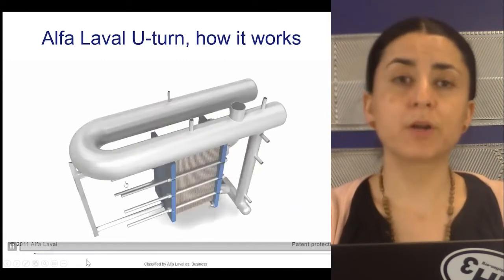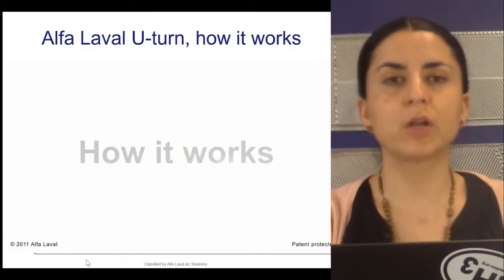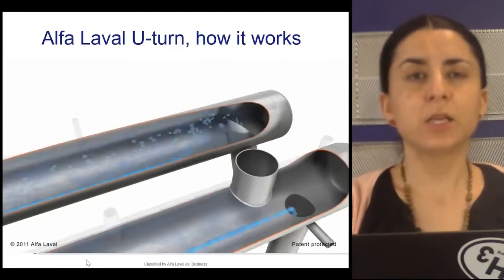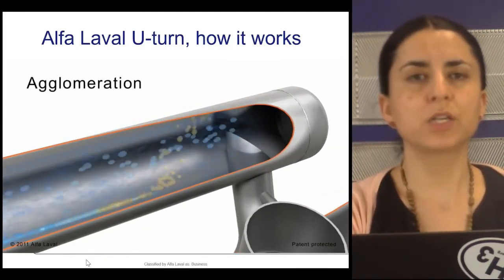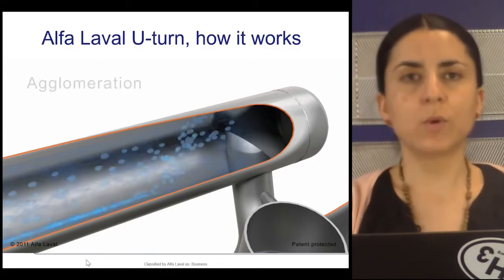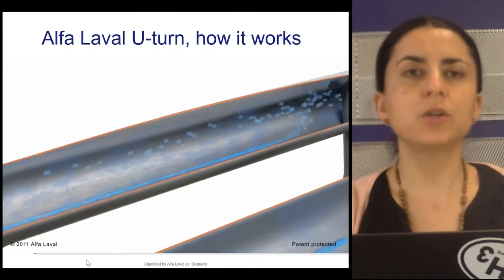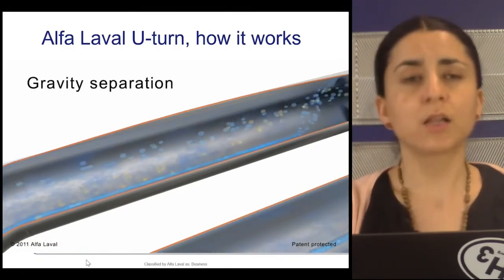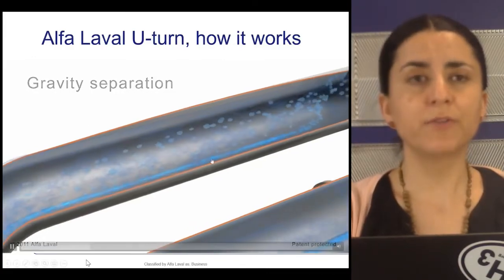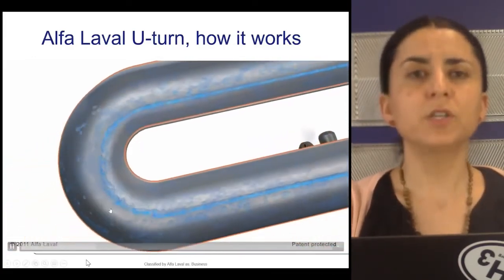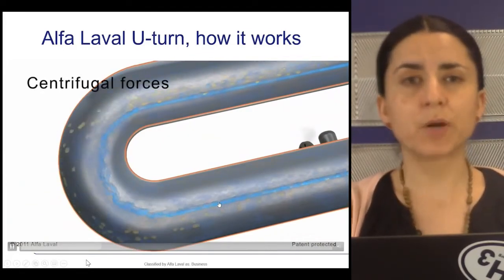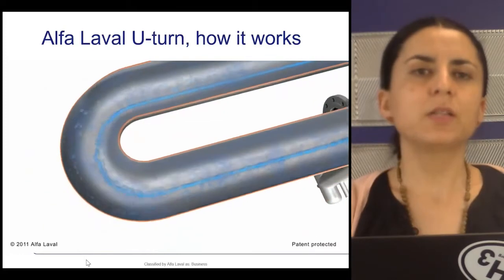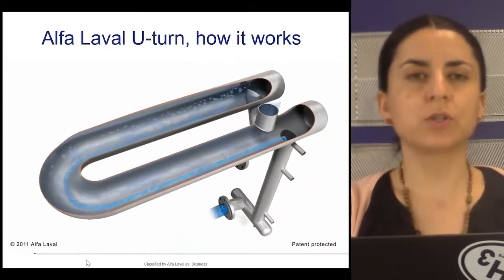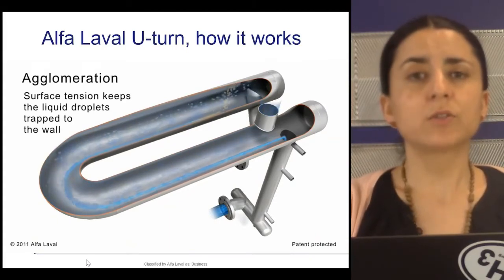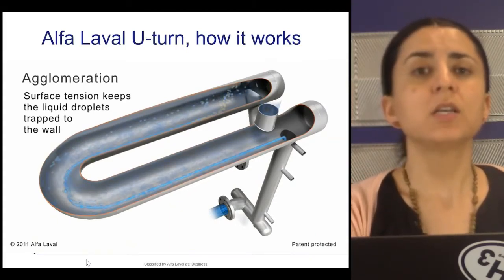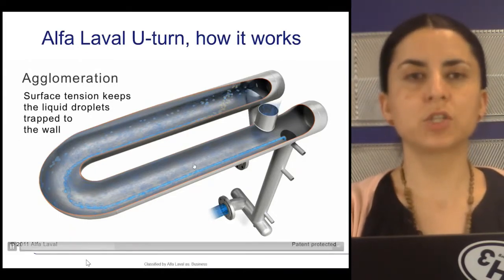Talking about separators, most of you have heard about our U-turn separator. Alfa Laval U-turn is a liquid separator that comes pre-mounted to the heat exchanger. Rather than the conventional one, which separates only by gravity, the U-turn uses 4 methods of separation: agglomeration, surface tension, gravity force, and centrifugal force. The efficiency of this evaporator has been a great surprise for our customers. Some of the advantages are small footprint compared to a traditional surge drum. Also, dramatic reduction on ammonia charge, achieving 0.5 pounds per ton of refrigeration.